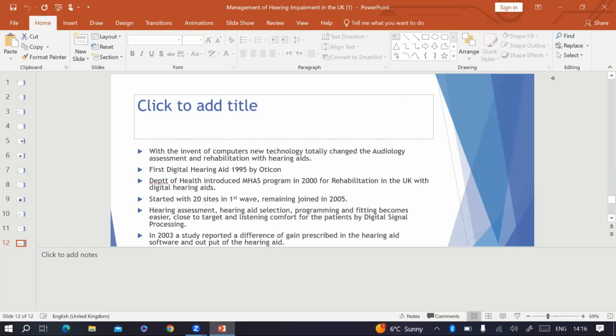Verification of digital signal processing was made compulsory in the UK by real ear measurements. It helps to program the aid within plus or minus 3 to 5, or 3 to 8 dB in the worst cases, thus providing more speech clarity. Hearing aid technology nowadays also works on speech clarity other than loudness, compression of noisy background, suppression of feedback, and elimination of any other artifact. So that's the brief description of what we are doing in the UK for hearing aids.